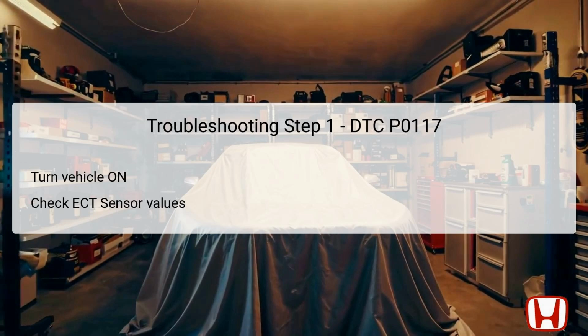Conversely, if the value does not meet this threshold, it suggests that the system may be functioning intermittently. In this case, a thorough examination for poor connections or loose terminals at the ECT sensor and the PCM is recommended.